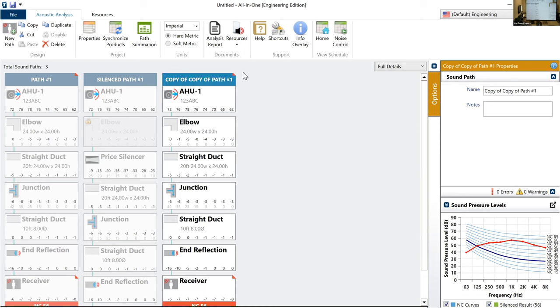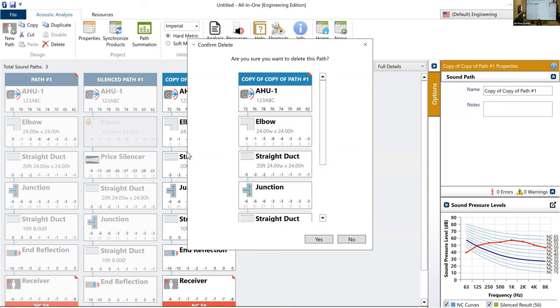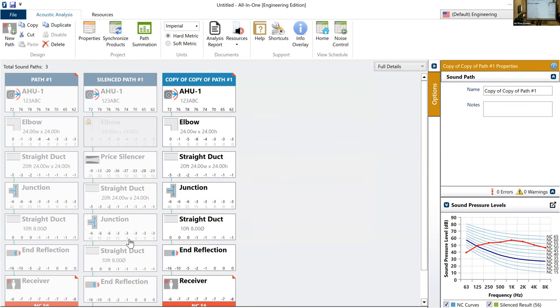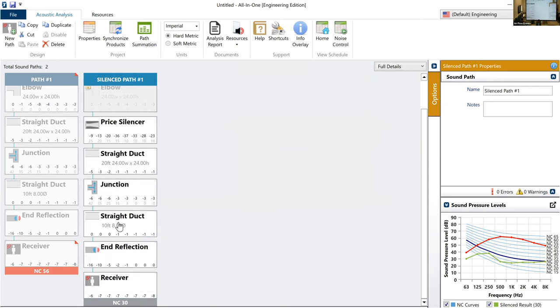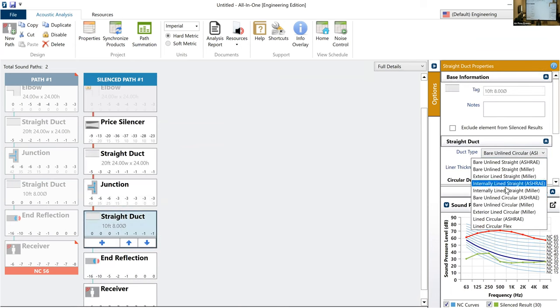Maybe let me delete this path. Is there a factor like for flexible duct in there? You know, like the lining in there, but all flex duct. There is, yeah. So if you had, say, this duct here was actually flex duct. At the bottom here, you can have either a lined flex duct or a whole bunch of different types of duct. You can also do things like duct liners if you have a 1-inch or a 2-inch duct liner.